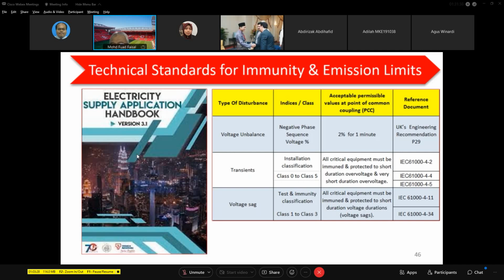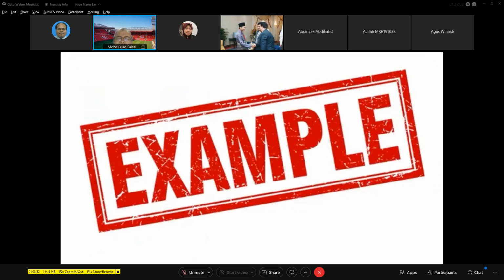And lastly, voltage sag. So you can see here there are two standards, IEC 61000-4-11 and IEC 61000-4-34, Class 1 to 3. These are very, very important to ensure immunity against voltage sag. These are the standards we want customers to comply with to protect themselves from power quality problems. Okay, let me give you an example. I'm almost finishing. This is a very fast example.